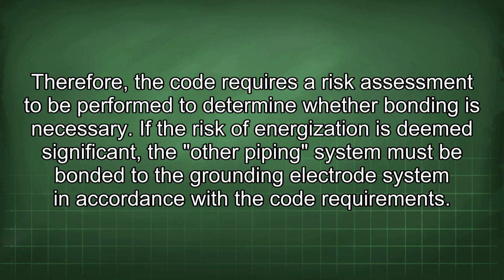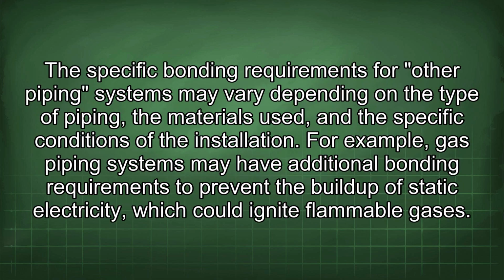Therefore, the code requires a risk assessment to be performed to determine whether bonding is necessary. If the risk of energization is deemed significant, the other piping system must be bonded to the grounding electrode system in accordance with the code requirements. The specific bonding requirements for other piping systems may vary depending on the type of piping, the materials used, and the specific conditions of the installation.